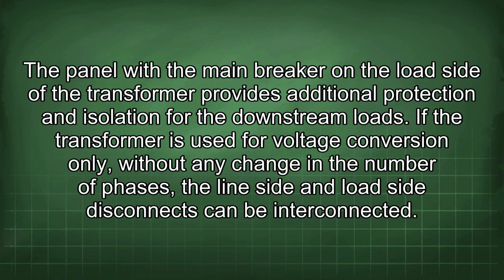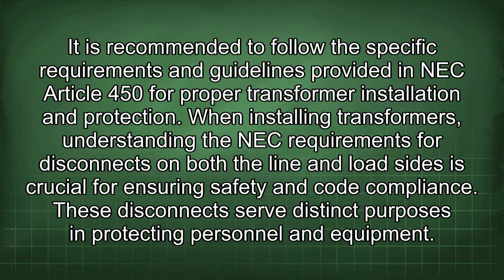maintenance. The panel with the main breaker on the load side of the transformer provides additional protection and isolation for the downstream loads. If the transformer is used for voltage conversion only, without any change in the number of phases, the line side and load side disconnects can be interconnected. It is recommended to follow the specific requirements and guidelines provided in NEC Article 450 for proper transformer installation and protection. When installing transformers, understanding the NEC requirements for disconnects on both the line and load sides is crucial for ensuring safety and code compliance.